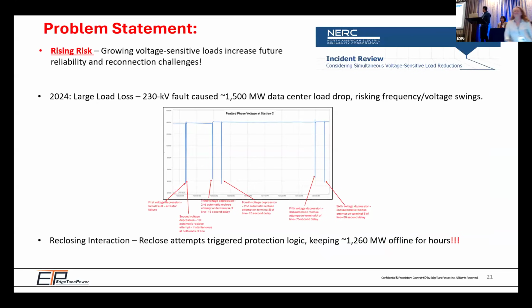Oh, sorry. So what happened in this event was that there was a very conventional fault happening at the 230 kilovolt feeder, a very conventional fault that you've probably seen on a monthly basis. But it was connected to a 1.5 gigawatt large load data center facility. And back in 2024, nobody knew what is really large load. But as you see, the utility cleared the fault. The data center facility wanted to reconnect. But the data center facility was like, I don't want to reconnect. I think you are not stable enough for me to reconnect to the utility.